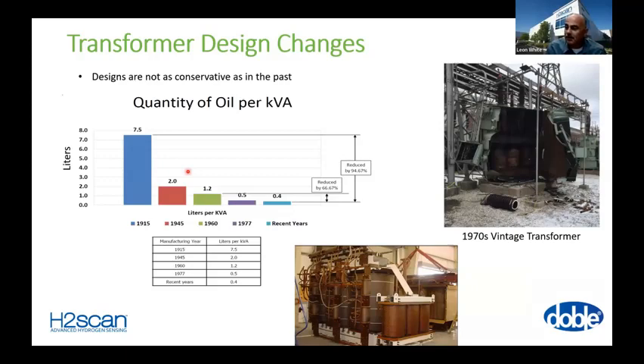So one of the big factors in transformer reliability is design changes. So as we have moved to a world of computer-aided design from the world of using slide rules, as far as I know, maybe Tony still uses one. I was aware of slide rules when I went through engineering school, but I never learned how to use one. But what we do know is, I spent 10 years in substation design, and when I was buying transformers in the 90s and replacing failed transformers when I worked at the utility, most of the new transformers were roughly half the size for the same rating as the transformer it was replacing. And so we really didn't have an issue. The foundation was just fine to hold a transformer half the size. And so we never had to enlarge the foundation as long as we weren't significantly increasing the rating.